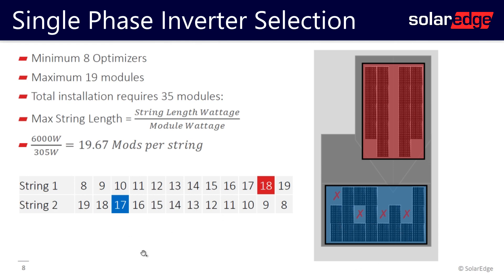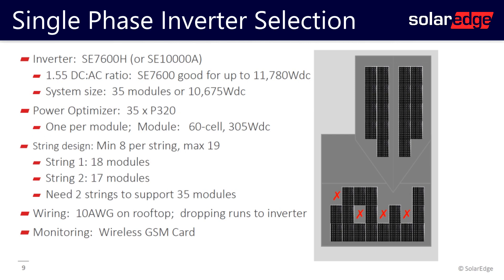To review what we selected: a 7.6 kilowatt inverter with a maximum DC to AC ratio allowed of 155%. The system size was 10,675 watts. We decided to use two strings — one of 18 modules and one of 17 modules. The last thing to consider is the wiring from the array down to the inverter.